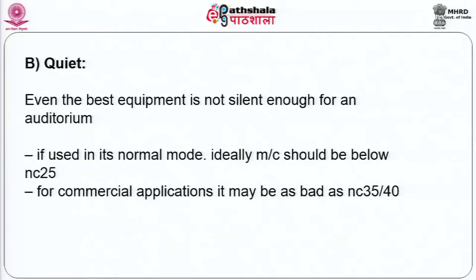Now, equipment generally is made to commercial standards, and asking for very special quiet equipment would normally mean a very expensive custom made equipment, which is normally not done. People tend to use normal equipment, but would like to make it quiet enough for use in an auditorium. The figure that one would really like to worry about is that in an office you have something like about 50 decibels noise limit, which is perhaps permitted, whereas in a good auditorium, it should be 35-40, or for a recording one, it should be even lower, maybe 15 to 20. This is what we meant.